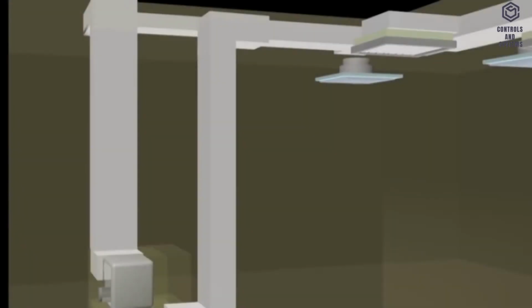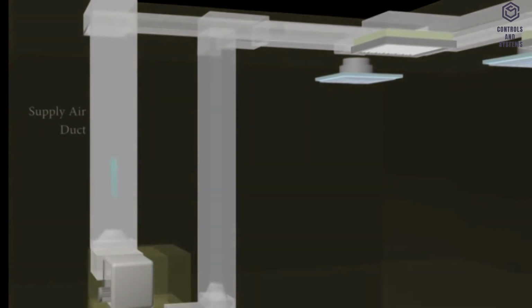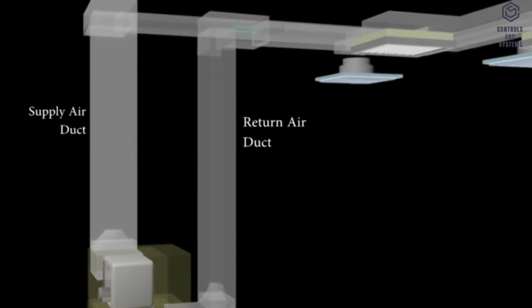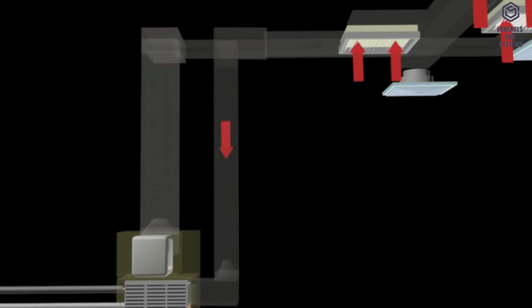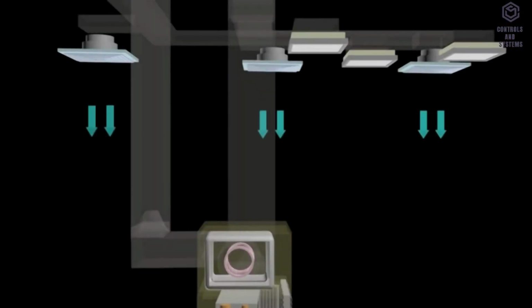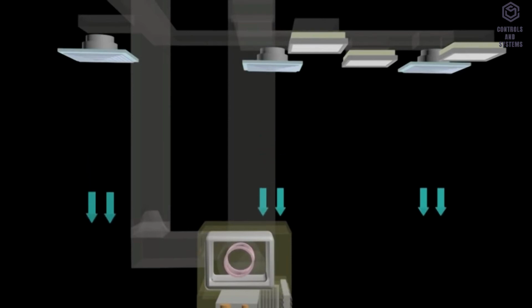The channel through which the air flows is called ducting. There are two types of ducting, which are the supply air duct and the return air duct. The air ducts are coated with insulating material consisting of fiberglass wrapped with aluminium foil. It reduces heat transfer from the environment to the air duct. Air returning to the air handling unit will pass through the filter before passing through the cooling coil and returning back to the room. This ensures that the air returns into the room in clean condition.